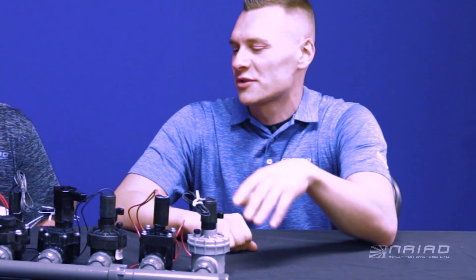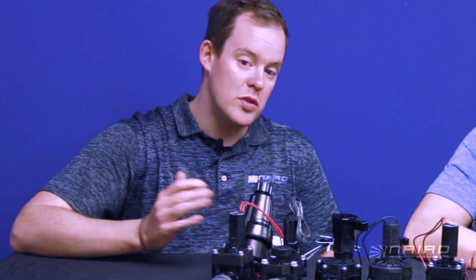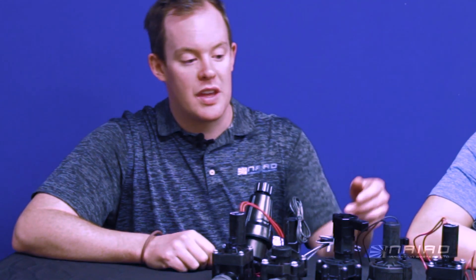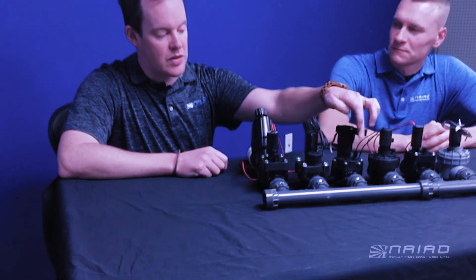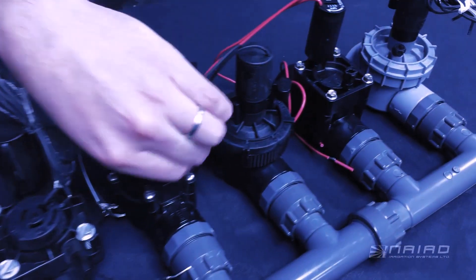So I see we've got some of these commercial grade control valves that we sell here. Would you mind telling me some of the more important components for this video? Absolutely. The most important thing to know before we get into it is how to turn on one of these valves manually. The two things we've got here are a solenoid and a bleed screw. You can turn the solenoid counterclockwise to open the valve manually — same thing with the bleed screw. The only difference between the two is the solenoid has wires on it.